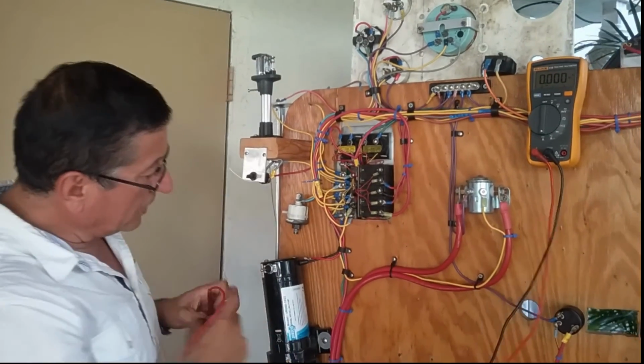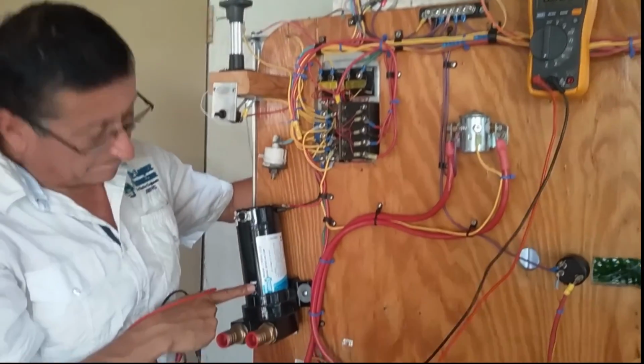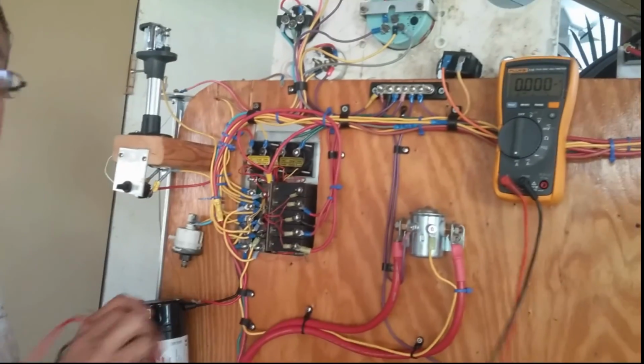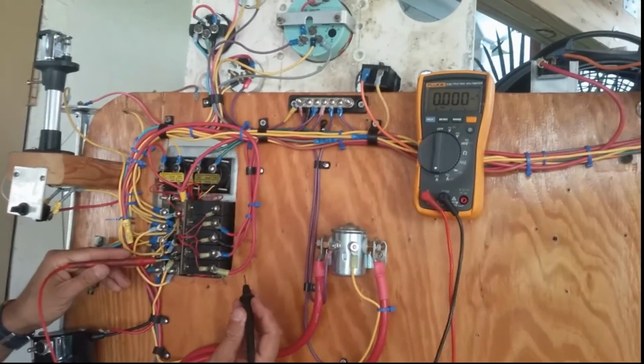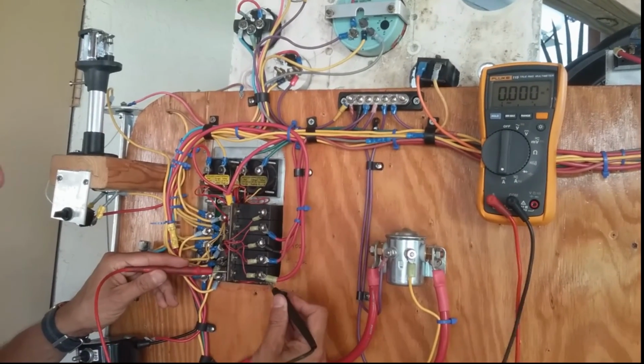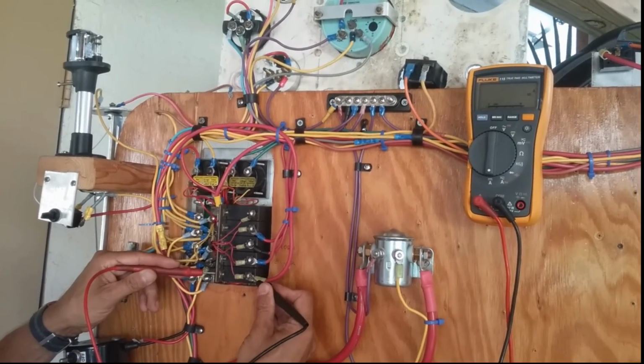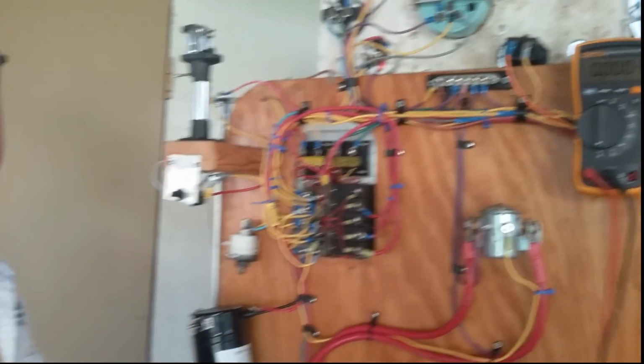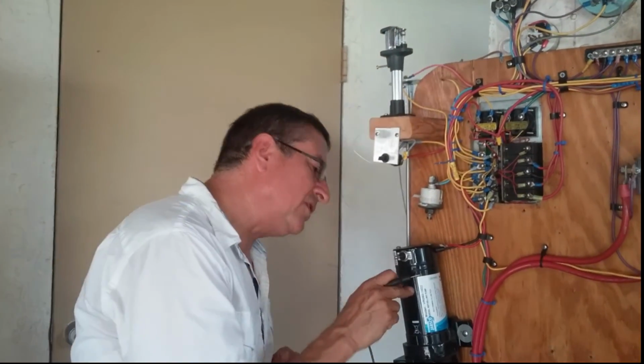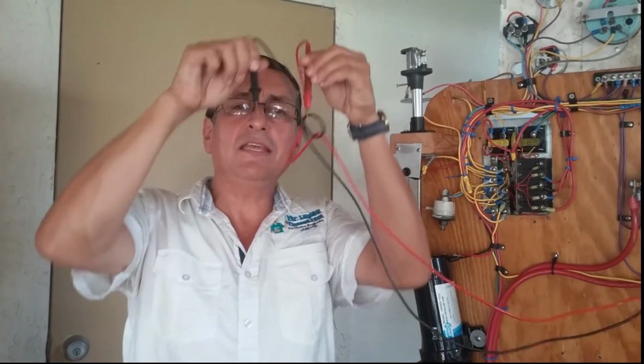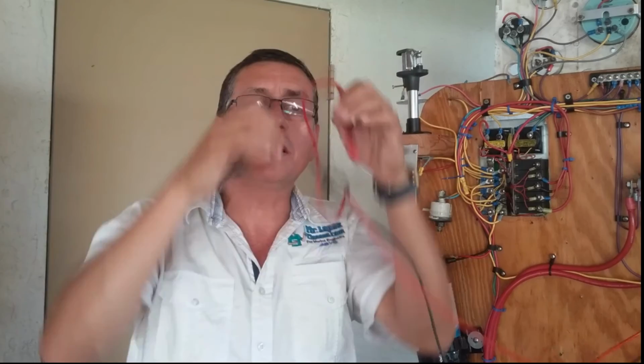Alright, the breaker for this pump is the bottom one, this one. Okay, in this moment the breaker is off. The contacts are open. I am going to close the contact with my hands and I am going to read the amps. 10.2 amps. This is the consumption of this pump. Yes, the only thing I need is to insert my ammeter where the cable is interrupted. And I know how much is the consumption of that equipment.